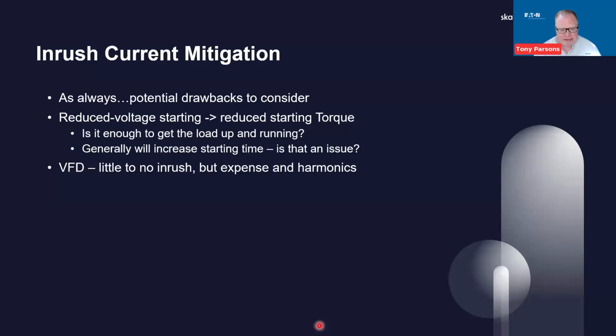And even with VFDs, again, little to no inrush current, but you're going to have additional expense for that added equipment. And then they can be a polluter of their own. They can create their own power quality problems with power system harmonics being one of the major sources of that type of disturbance.